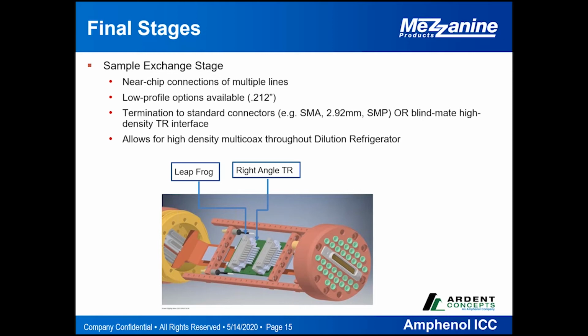Those TR multi-coax connectors are wired out to the outside frame of the sample exchanger. In some cases, customers wire out to pluggable SMPs, or more preferably, route the multi-coax connector to a blind mate multi-coax connector, so the TR interface on either end can be mated to a TR outside the sample exchanger. In this case, it's a higher density interface. On the right-hand side of this model, there are multiple SMPs designed into the outside of that scope, which could be replaced with a much denser TR multi-coax interface.